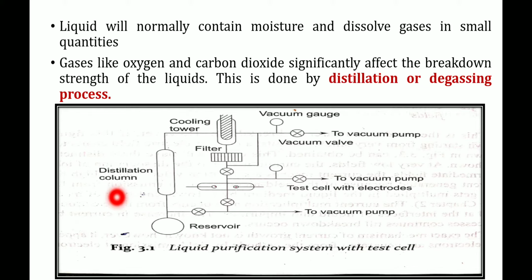Next comes moisture content and dissolved gases, such as oxygen or carbon dioxide. Due to the presence of these dissolved gases, the breakdown strength or electric strength of the liquid is reduced. So these impurities are removed by a process called distillation, or the degassing process.